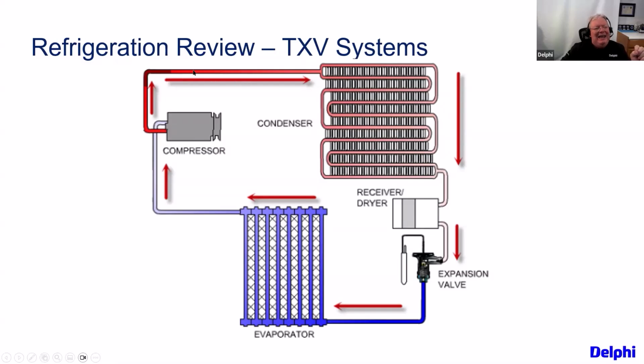Depending on where the gauge fitting is, the service port will tell you. Some service ports on the high side are right here, or maybe even after the expansion valve. But usually before the expansion valve, it's going to be a different pressure because it's been cooled than it is going to be here. So keep in mind, know where your service ports are, and know the theory of operation of AC - that gives you a better idea: is this too high or is this too low?